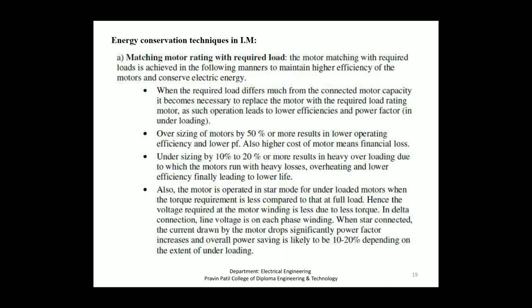Also, the characteristics of motors vary widely with their load and the type of duty they are expected to perform. For example, applications like constant speed, constant torque, variable speed, steep or sudden stop, continuous or intermittent duty, frequent start or stop, etc., should be taken into consideration carefully when deciding the type of motor for that specific application. Proper selection of the range of the motor according to load requirement will reduce the power consumption.